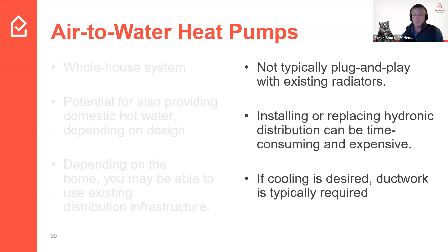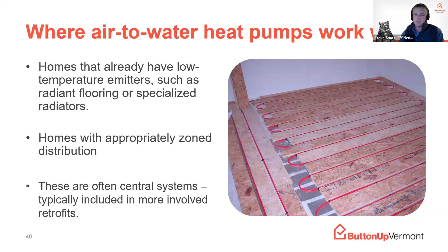Radiant floors: if you have a radiant heating system in an existing home, oftentimes it can be possible to retrofit an air to water heat pump in, because radiant floors are a low temperature type system in the first place. So that is something to be considerate of. If you know that you do have radiant floors in your home and it's currently a fossil fuel fired system, that could be a possibility to be a little bit more of a quote unquote plug and play retrofit with an air to water system.